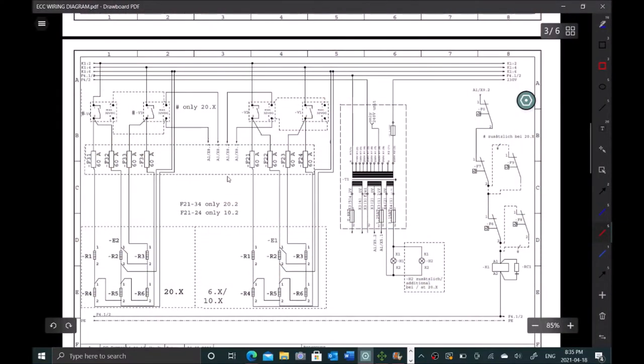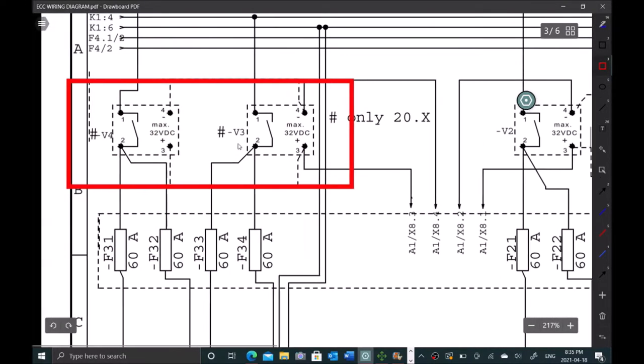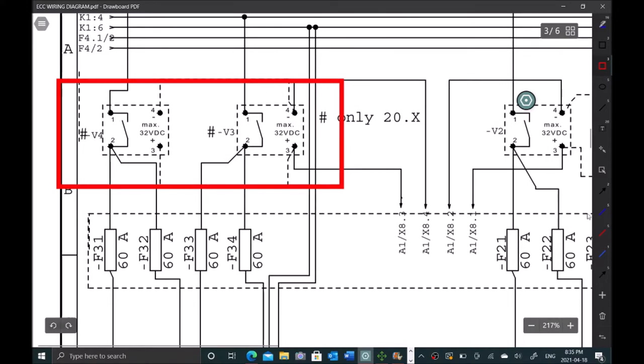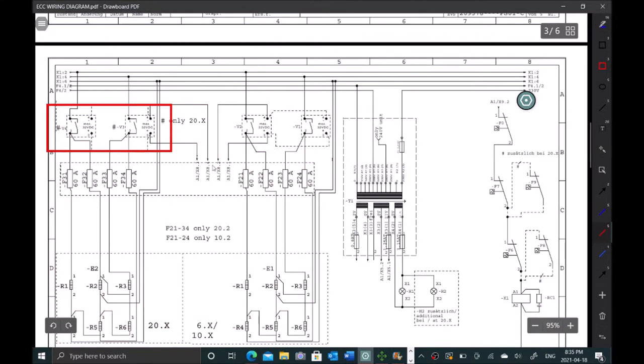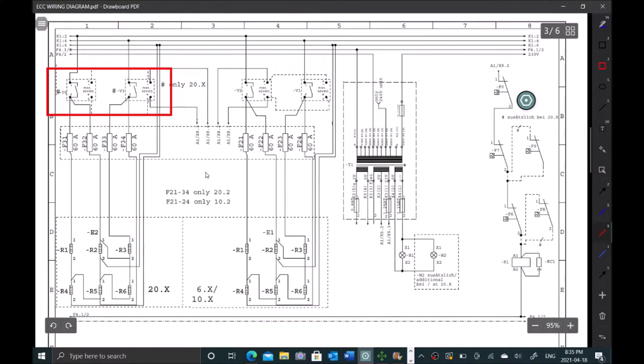Alright, so we're going to start by pulling up a schematic. Every time we're blowing that main fuse in the breaker or in that disconnect, we're blowing these two relays right here. So these two relays, they're actually failing closed. So when we don't have a call for heat, these are failing closed like that. Let's just go and see why would these relays blow. This should give us a hint towards what might be the fault as to why we keep blowing that fuse and why it's blowing intermittently.